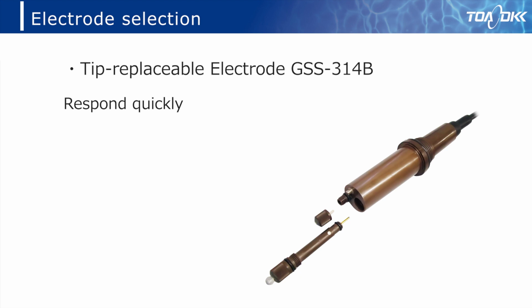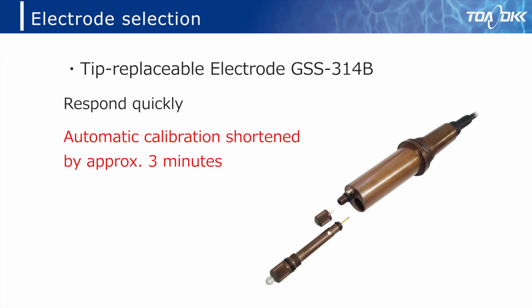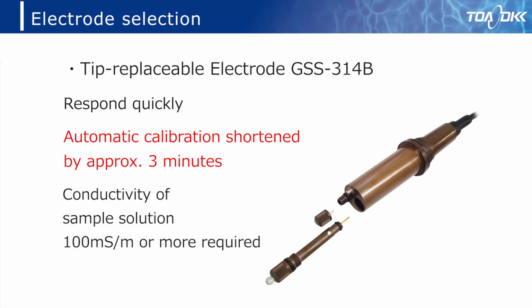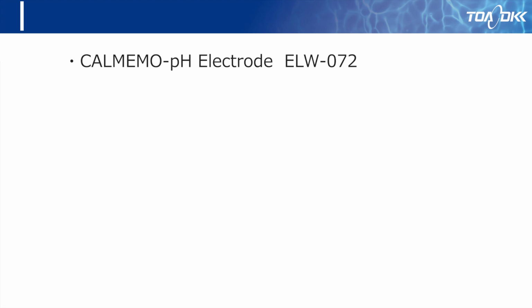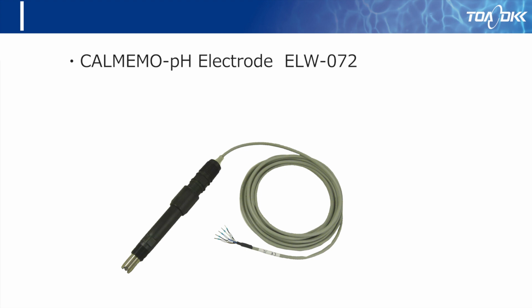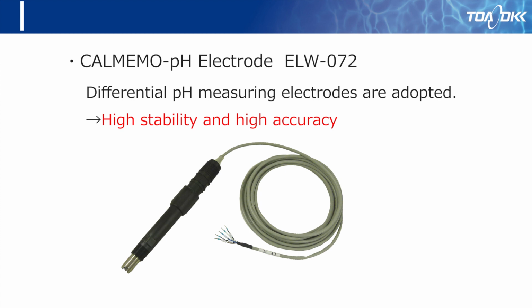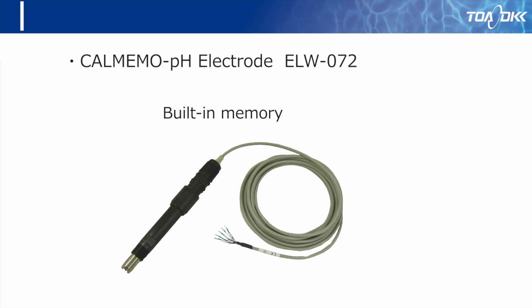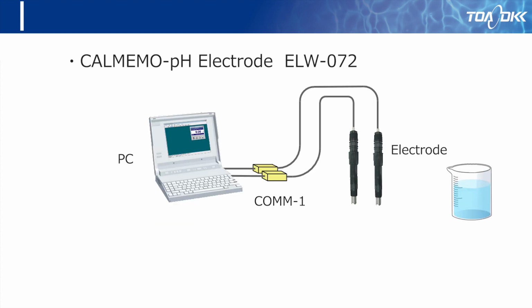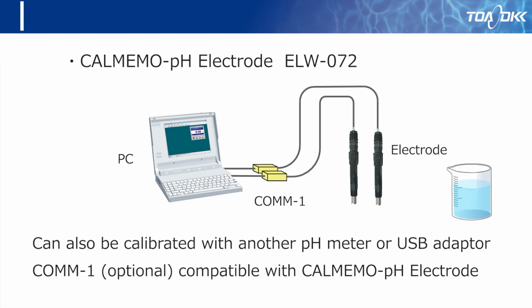GSS314B responds more quickly than EL5600. Therefore, the time for automatic calibration can be shortened by approximately 3 minutes. However, the electrical conductivity of the sample water must be 100 mS/m or more. If it is lower, the EL5600 type may be suitable. The third specification is the CALMEMO-pH electrode. This electrode adopts a differential pH measuring electrode, which enables highly stable and accurate pH measurements. This electrode has an embedded memory inside. Since the calibration data is stored in the electrode itself, it is also possible to calibrate with other pH meters compatible with the CALMEMO-pH electrode or the optional COMM-1 type USB adapter.